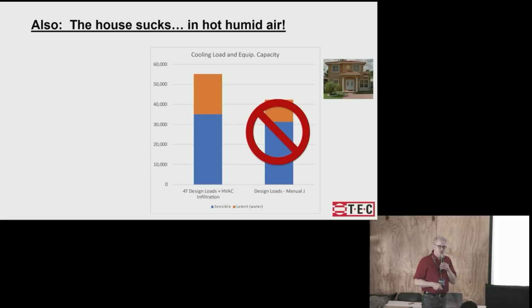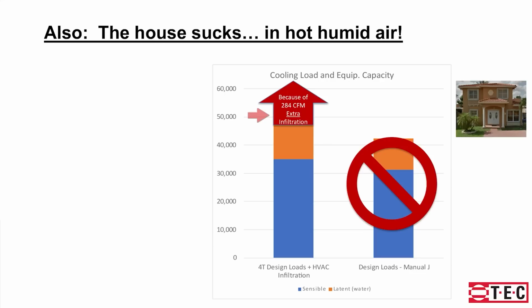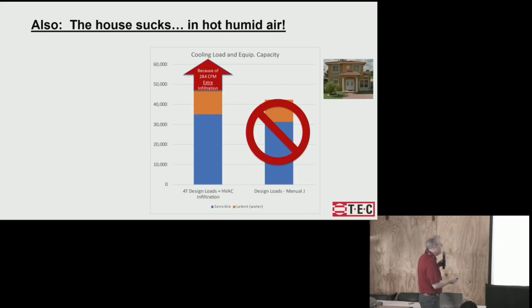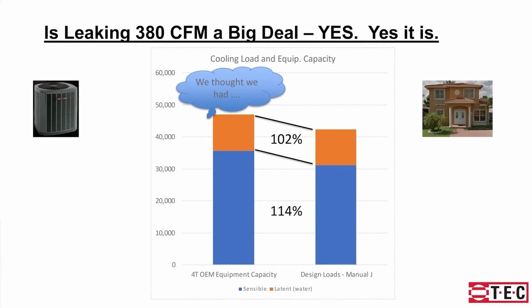Yeah, and so does that explain having a humidity problem? If you thought you had this much latent to take care of and you actually have this much, that for sure explains a humidity problem. Because of the extra 284 CFM of extra infiltration coming in, we've got a house that should be 4-ton, but the load's really closer to 5. Okay, so this is what we thought we had. We thought we had the equipment covering over 100% of the latent and 114% of the sensible. We thought we were good, right?